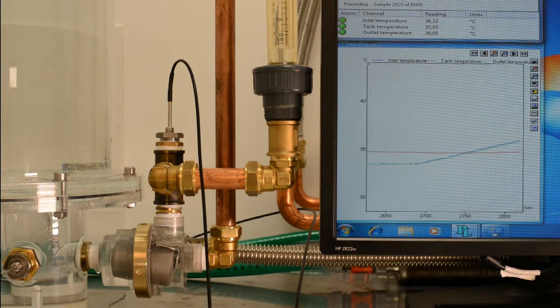So now the inlet temperature is at 36.2, where the tank temperature is 35, and now you can see the valve is really switching, and now it is switched completely through. So it uses this offset of around 1 degree to make sure that no heat can be withdrawn, because we need this offset when we start cooling to make sure that the valve is switched back to the bypass position when we are cooling before it drops below the red line.